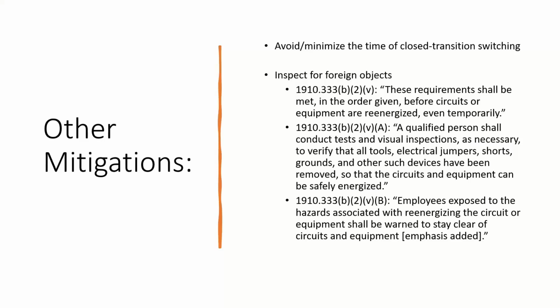Nowadays you're finding companies more likely to say, no, we've got to buy higher rated equipment and make sure that doesn't happen. But you need to keep that in mind. Even if you have rated equipment, you have to realize that when that tie breaker is closed and the two systems are tied together, you've definitely got a lot more fault current available, which means your arc flash hazard goes way up. You're likely not going to be able to avoid doing it, but you can definitely minimize the amount of time that the two are closed together.